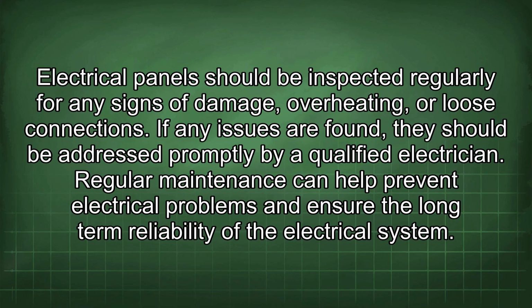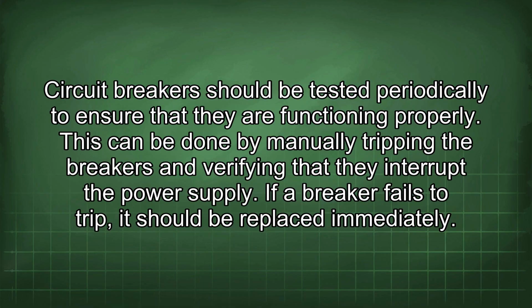The electrical panel should be inspected regularly for any signs of damage, overheating, or loose connections. If any issues are found, they should be addressed promptly by a qualified electrician. Regular maintenance can help prevent electrical problems and ensure the long-term reliability of the electrical system. Circuit breakers should be tested periodically to ensure that they are functioning properly. This can be done by manually tripping the breakers and verifying that they interrupt the power supply. If a breaker fails to trip, it should be replaced immediately.